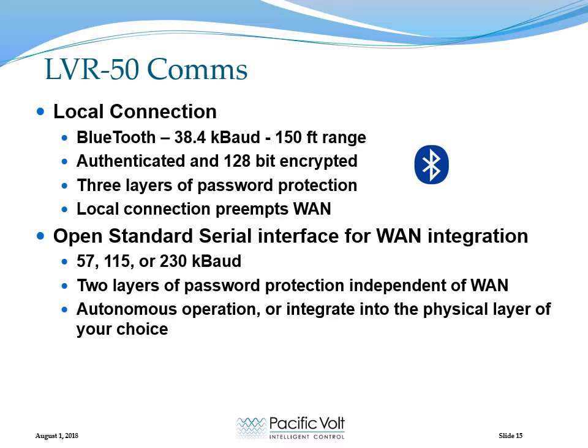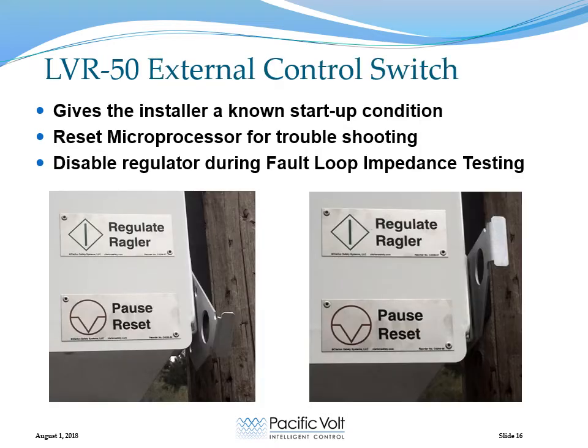The important point is that the regulator is designed to operate autonomously. You are not required to maintain the cost burden of a centralized control system for this to operate. You largely set the set point and forget about it. The regulator has an external control switch which can hold the regulator in a disabled condition, which means the input voltage is equal to the output voltage. When you switch it from pause to regulate, the microprocessor is reset and it boots up and starts to regulate. This gives the installer a known startup condition, and it's helpful for troubleshooting if necessary. The other reasons for this are only applicable to the 50 Hertz world, so we will skip them for now.